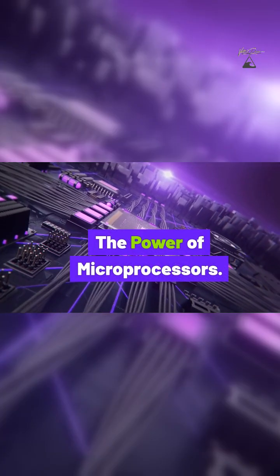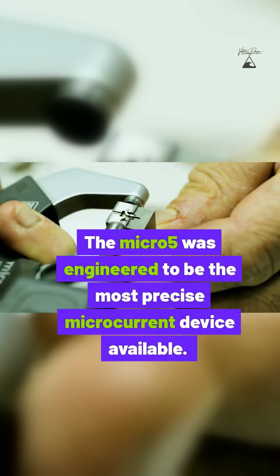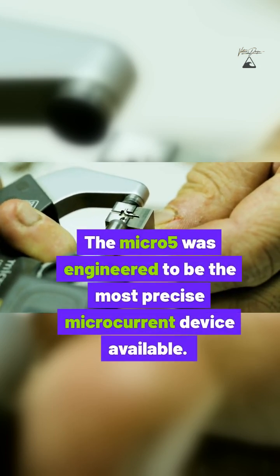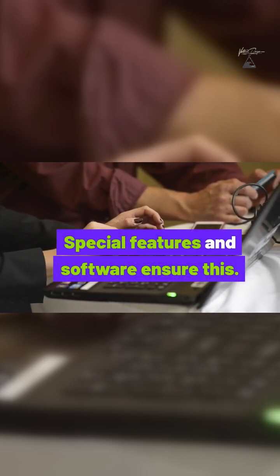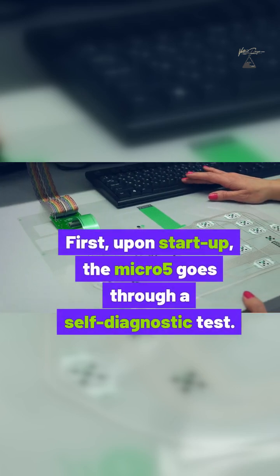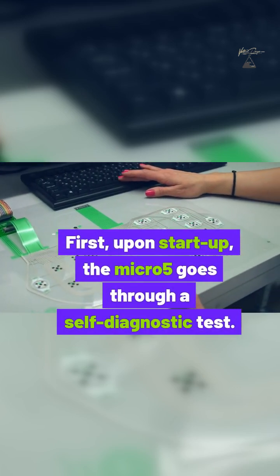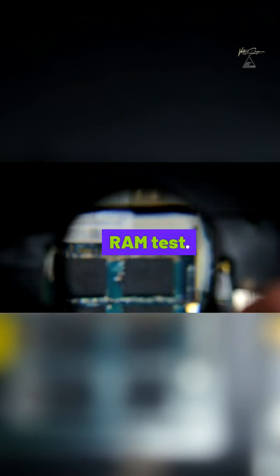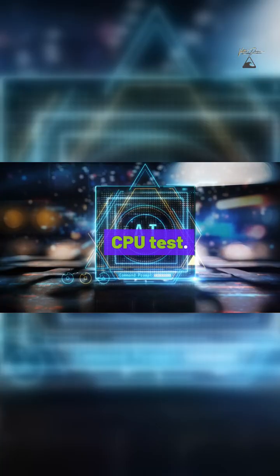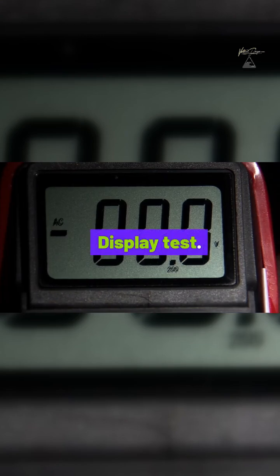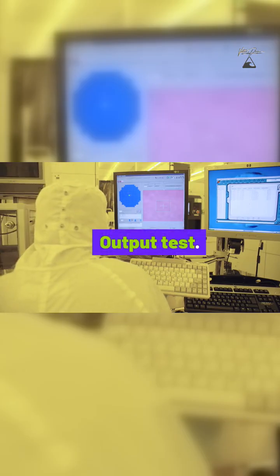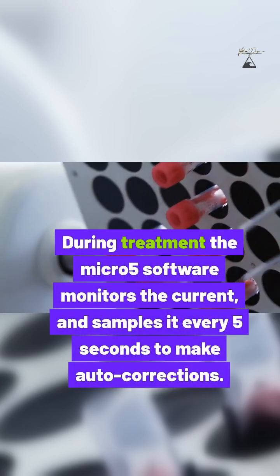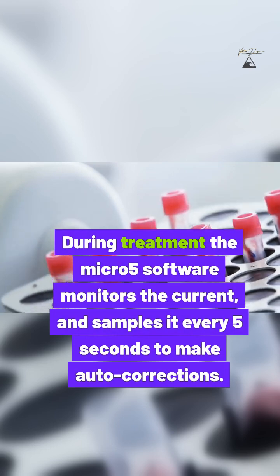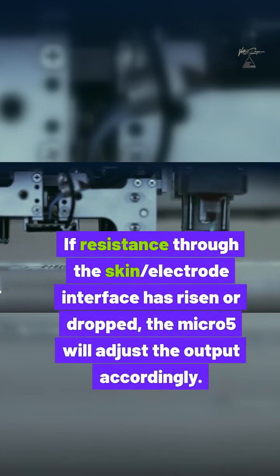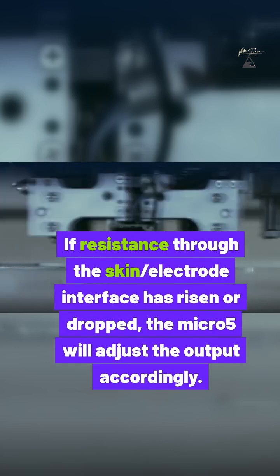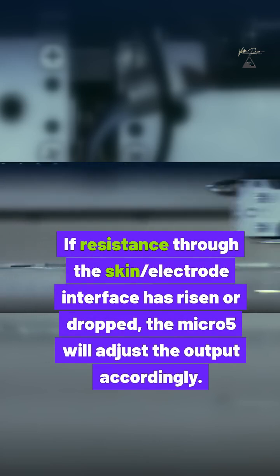The power of microprocessors. The Micro5 was engineered to be the most precise microcurrent device available. Special features and software ensure this. First, upon startup, the Micro5 goes through a self-diagnostic test. RAM test. ROM test. CPU test. Display test. Output test. During treatment, the Micro5 software monitors the current, and samples it every 5 seconds to make auto-corrections. If resistance through the skin, electrode interface has risen or dropped, the Micro5 will adjust the output accordingly.